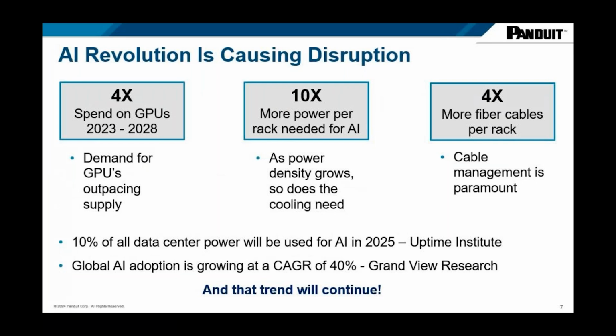We're seeing 10 times more power needed per rack. As density grows, so does the cooling need. Data center providers were used to seeing their average server cabinet in the 5 to 14 kilowatt range. As you'll see later, 100 kilowatts per cabinet is not out of the question with these dense AI systems.